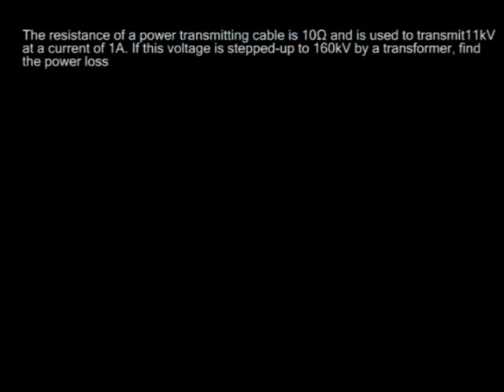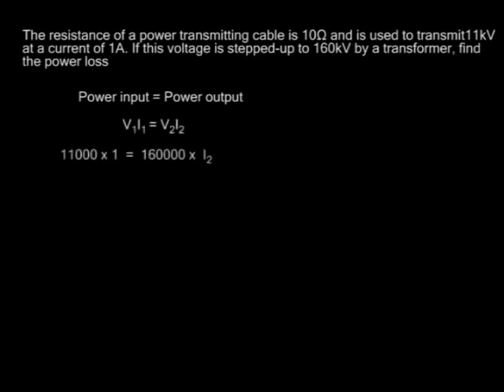For example, the resistance of a length of a power transmitting cable is 10 ohms and is used to transmit 11 kilovolts at a current of 1 ampere. If this voltage is stepped up to 160 kilovolts by a transformer, determine the power loss. Now, assuming the transformer is 100% efficient, power input is equal to power output. V1I1 = V2I2. 11,000 times 1 is equal to 160,000 times I2. I2 is equal to 11,000 over 160,000.